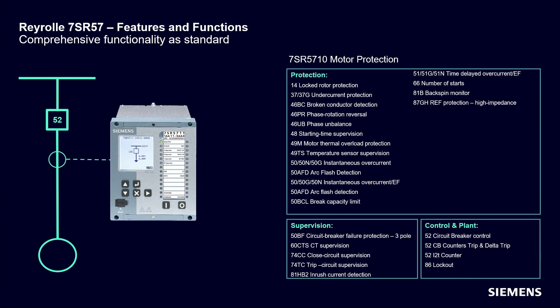Function 14 locked rotor protection uses definite time over-current elements to monitor motor stalled conditions. The operation of these elements can be controlled from motor stopped or running conditions. Function 48 allows the motor startup time to be monitored; an output is raised if the start time exceeds the setting. Function 66 monitors motor starting and provides settings to control both the number of times a motor can be started within a specified time period and the minimum time between starts.